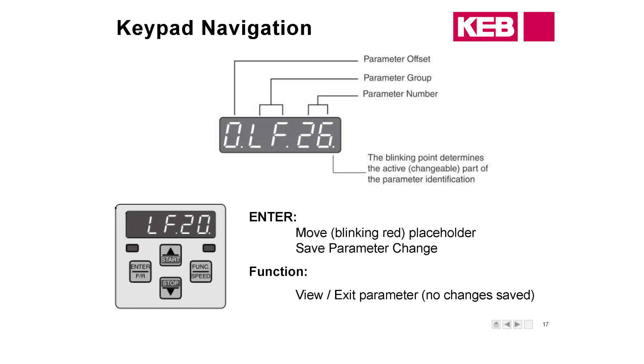If you wish to view a parameter, go to the parameter number you want and hit Function — that will bring up the value stored in that parameter. If you wish to change it, use the arrow up or arrow down and hit Enter to save the new value. If you don't hit Enter, the new number you see will not be stored, so it's absolutely critical that you hit Enter.